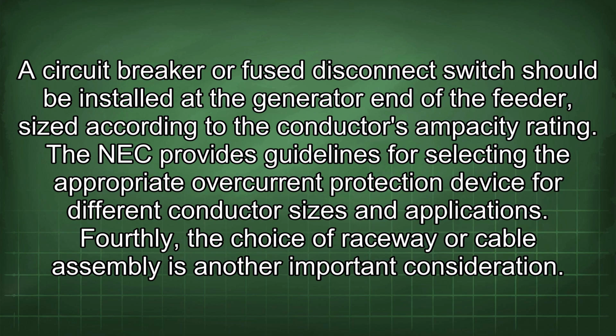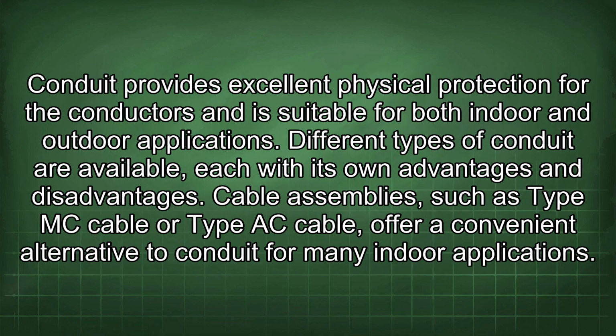applications. Fourthly, the choice of raceway or cable assembly is another important consideration. Conduit provides excellent physical protection for the conductors and is suitable for both indoor and outdoor applications. Different types of conduit are available, each with its own advantages and disadvantages.